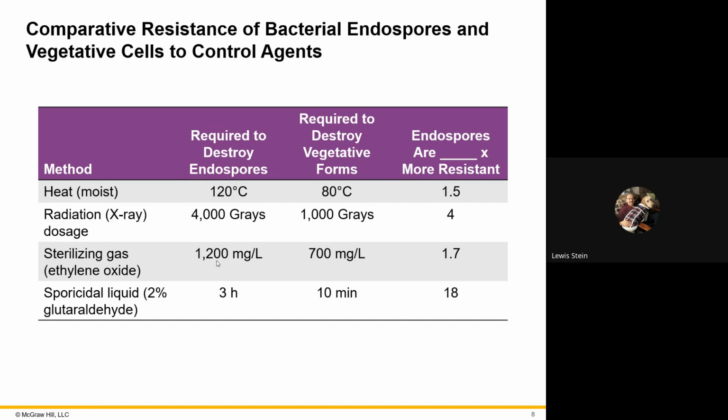Called ethylene oxide. We put them in a gas chamber. No two ways back. And this is something I use a lot. This is what happens, why it's a tincture of time. You have to have time available. Ten minutes would be fine for just general disinfection. If you want to sterilize, a minimum of 3 hours, typically up to 12.